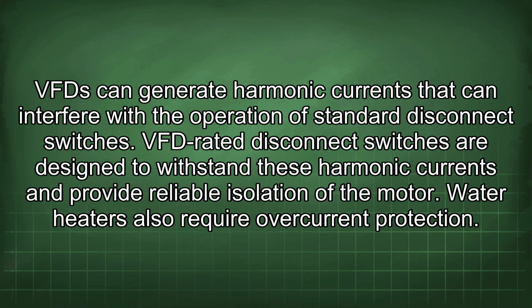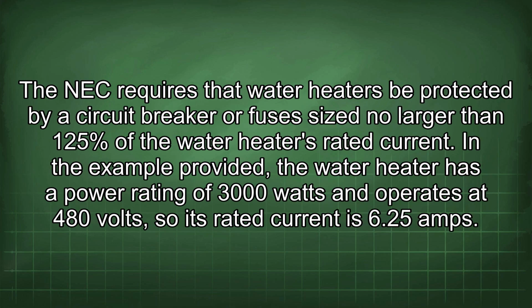Water heaters also require overcurrent protection. The NEC requires that water heaters be protected by a circuit breaker or fuses sized no larger than 125% of the water heater's rated current. In the example provided, the water heater has a power rating of 3000 watts and operates at 480 volts, so its rated current is 6.25 amps.